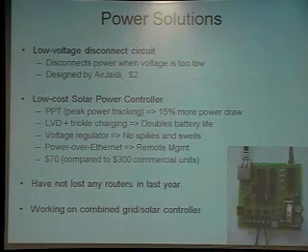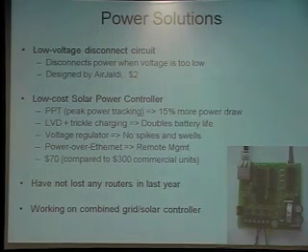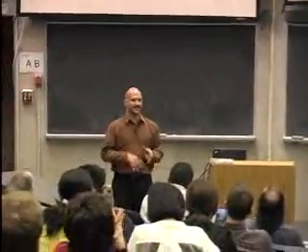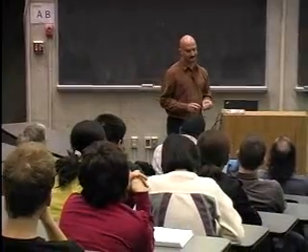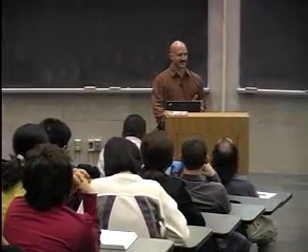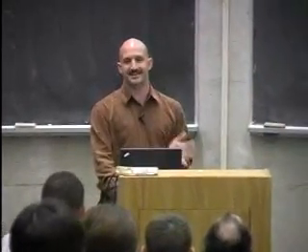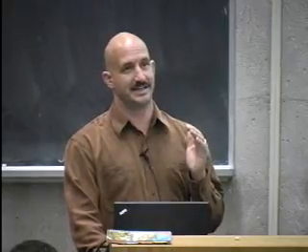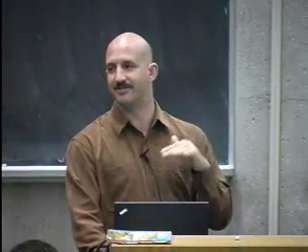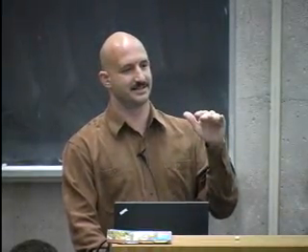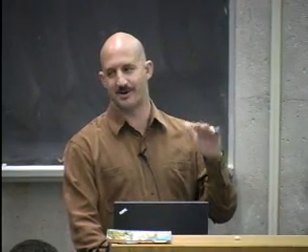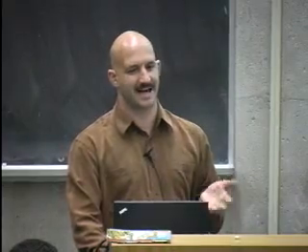And we're also working on a combined version that basically will replace the UPS. So a low-cost UPS that can tolerate this kind of environment. Because it's not actually rocket science to do that. It's that UPSs are not designed for this environment. For example, the APC UPSs typically will not work below 180 volts for a 220 UPS, right? But I know that the power is below 180 volts a whole bunch of the time, right? So that is just categorically not going to work.